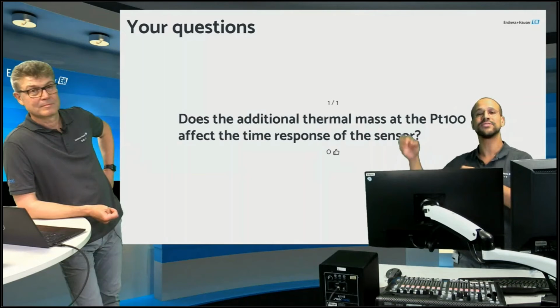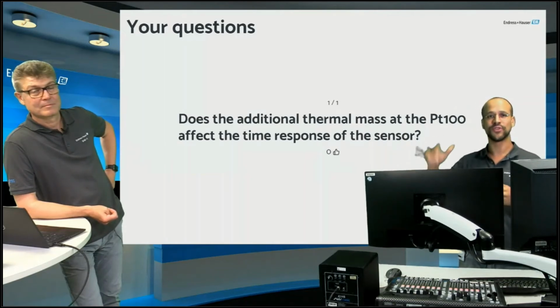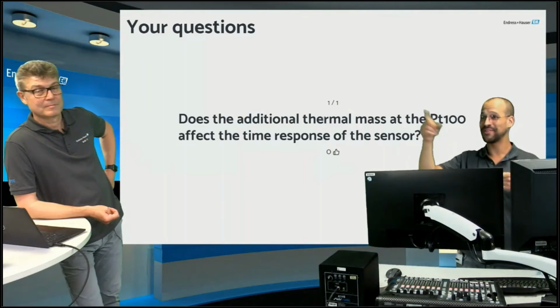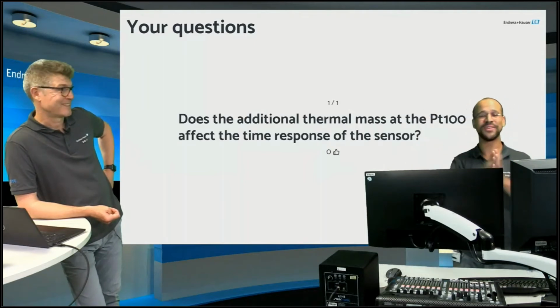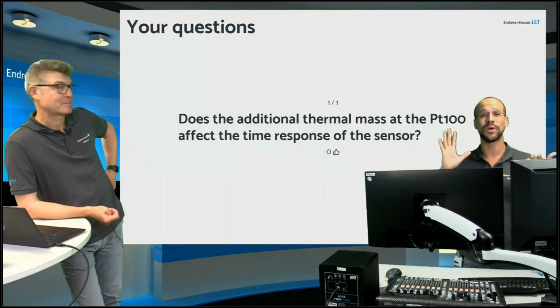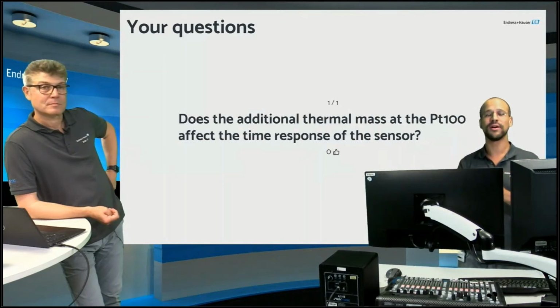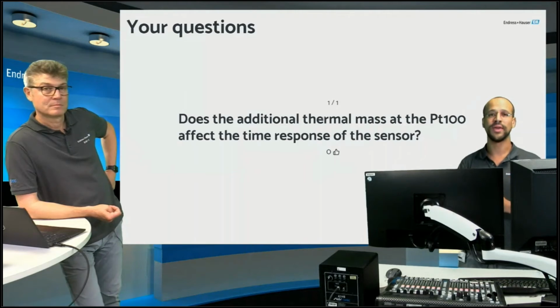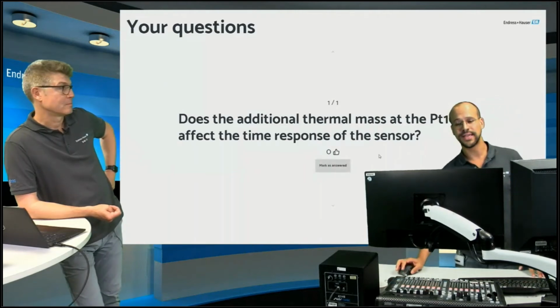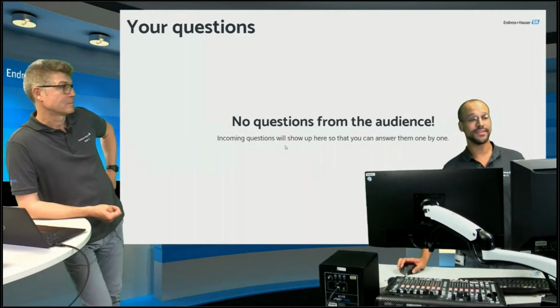And therefore, the thermal mass itself of the reference has no influence on the response time, but of course the TrustSens is not a sensor-on-tip technology. So just a rough idea, I looked it up because that question came in earlier. The response time of a QuickSens is 1.5 seconds T90 time in general, depending on configuration, and for TrustSens it's 9.5 seconds. So not slow, but of course not as quick as a quick-responding sensor technology.